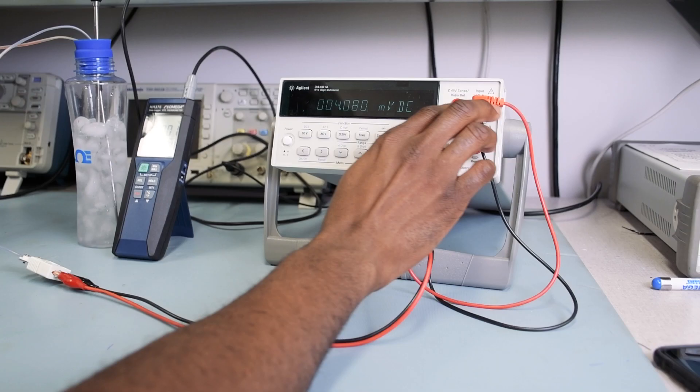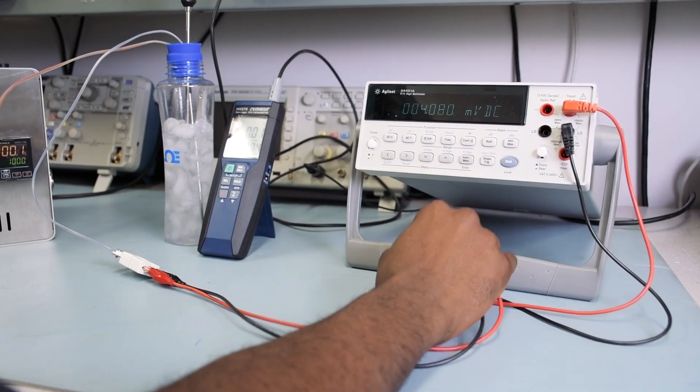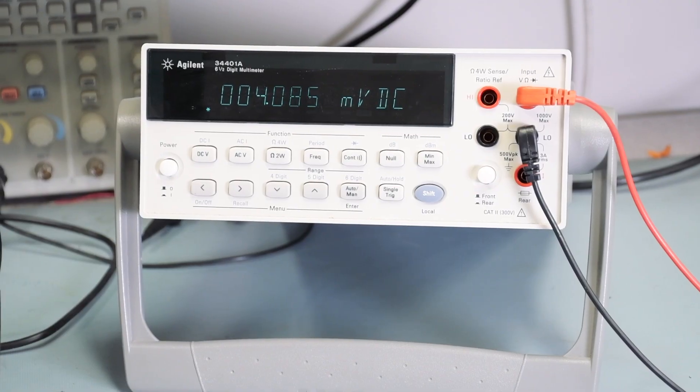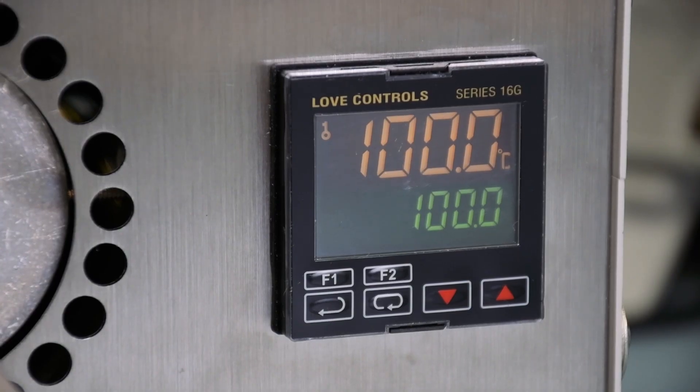Then we have the other side of the reference probe connected to a digital multimeter that's giving us the raw millivolt signal from the thermocouple. And as you can see on the multimeter, the millivolt signal matches the temperature of the dry block. So this thermocouple passes our mock calibration.